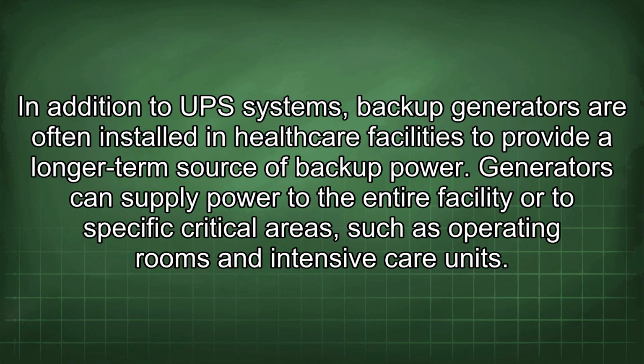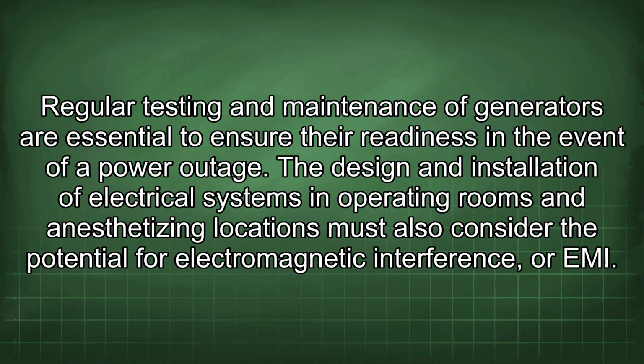In addition to UPS systems, backup generators are often installed in healthcare facilities to provide a longer-term source of backup power. Generators can supply power to the entire facility or to specific critical areas such as operating rooms and intensive care units. Regular testing and maintenance of generators are essential to ensure their readiness in the event of a power outage.